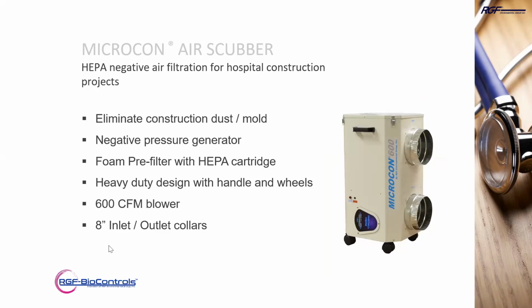Finally, the air scrubber. This is not for infectious disease, this is for hospital construction. If there are people in the hospital, they're there for a reason, and we need to make sure we're not kicking up dust and particulates into the air. One nice thing about the Microcon 600, if you can see on the slide, there's a plate or cutout at the bottom to put a halo in, so now you can increase the air purification. Next slide.